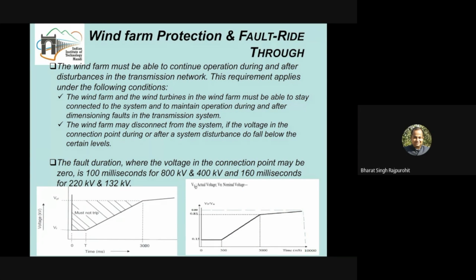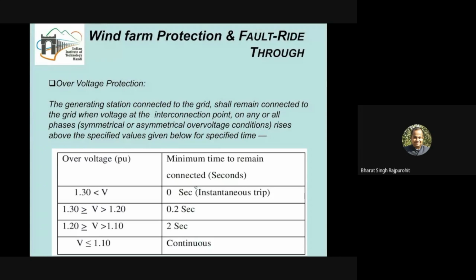So the Indian grid code is not as severe as the German grid code, and it gives better flexibility for the wind energy conversion system or solar farm to work. This time limit is also based on the voltage level at which the fault has happened, which is where the wind farm is connected. So it is different for different voltage levels, and these timings are different. This is how our Indian electricity grid code is working.